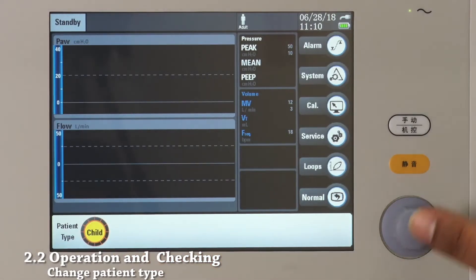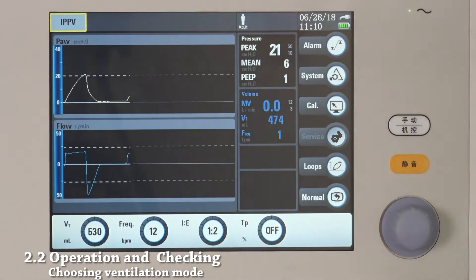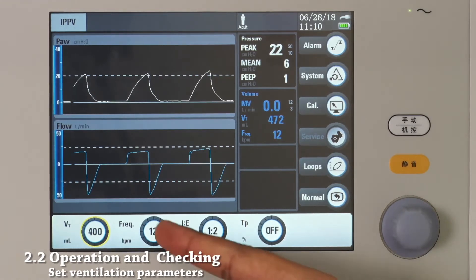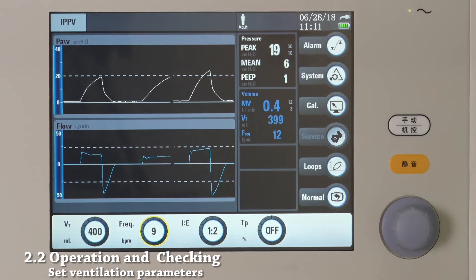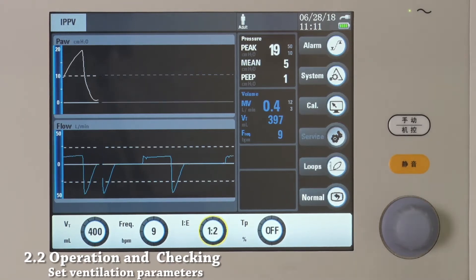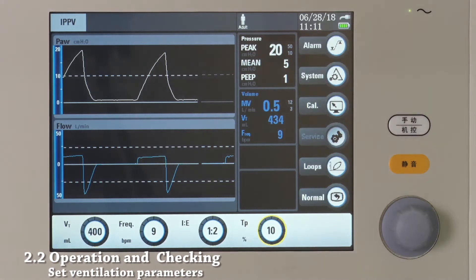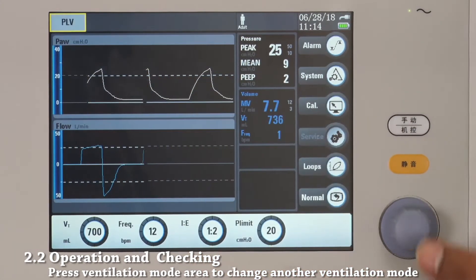Touch here and use the navigator knob to change the patient type. Press to confirm. Touch here to choose the ventilation mode — let's choose IPPV. This part will show you how to set the ventilation parameters. Touch here to change to another ventilation mode. To confirm, touch again or use the Navigator knob.